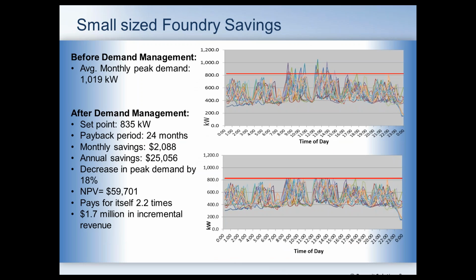So the slide we're coming into right now, these are some actual case studies. Each one of these colors on this graph represents one day of a 30-day month period of time. And you can see by looking at these colors, there are only a few occurrences where the system was spiking above the 800 kW set point. This was a small facility in Wisconsin. They were able to go in and save 200 kW at roughly $20 a kW. So they had a pretty significant savings by putting in an automated system. Next slide, please.